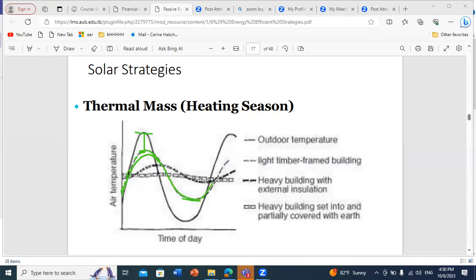To enhance the behavior of the thermal mass, we can use a heavier thermal mass. For a heavy building with external insulation, we can see that this pattern of variation is much better. The fluctuation within the indoor space will be much lower, with a much lower maximum and a much lower minimum in absolute value. So we can see that the thermal mass, when designed appropriately, can reduce a lot the fluctuation in temperature.